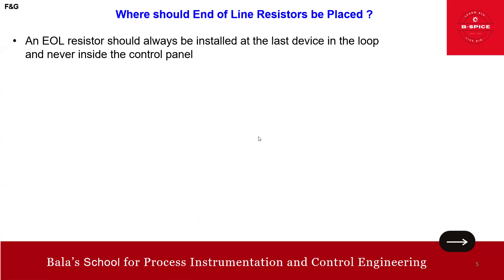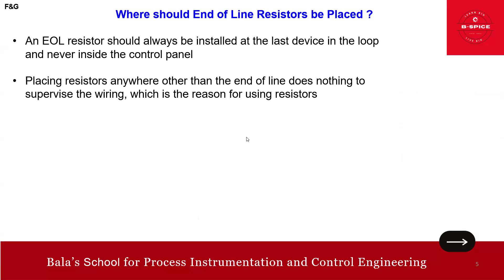Where should the end-of-line resistor be installed? It should always be installed at the last device in the loop and never inside the control panel. Placing the resistor anywhere other than the end of line does nothing to supervise the wiring, which is the entire reason for using it.